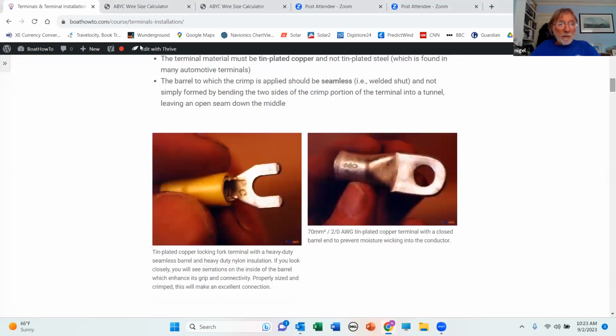So the first thing we want is to get terminals that have a locking function. Ideally, there'll be ring terminals, because then if a screw comes loose, they're not going to fall off. However, ring terminals are a pain in the backside to install in tight spaces, because you've got to take the screw all the way out, put the terminal in, and then you drop the screw in the bilges. So a couple of tools you might look for, which you can get from Lowe's and Home Depot. One is for screws that just have a slot in them, a slotted screw. It's called a split shank screwdriver.